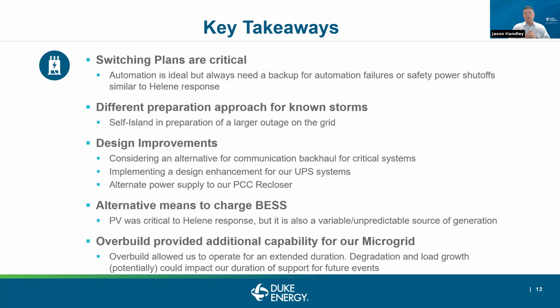And as you go through these events, you learn about design improvements and alternative communications backhaul for critical systems. We have redundant communications, but both failed: our fiber optic line was down because we had poles down, and our cellular was also down. So we were blind in a lot of cases until cellular came back up, and then it was spotty. So we went ahead and put in a Starlink system to ensure we could have reliable communications for remote operations.